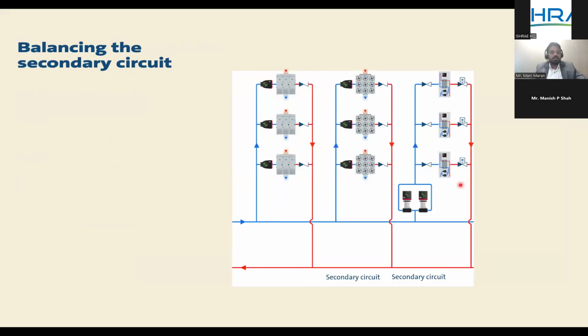So let's see first how we balance the secondary circuit. Distributed pumps on the secondary circuit manage the load by themselves by taking the temperature feedback from the air side. So let's say we give a set temperature of 30 degrees and the actual temperature is 32 degrees from that particular data hall. Then the pump will increase its speed and try to take more chilled water from the decoupler line. Whereas if a load is not having any increase, this pump stays off, and there will not be any chilled water driven by this pump from the decoupler line through this loop. So that's how we make these pumps independent and this unit independent, and the flow is modulated precisely based on the temperature feedback. That's how we modulate the flow for each unit on the secondary side.